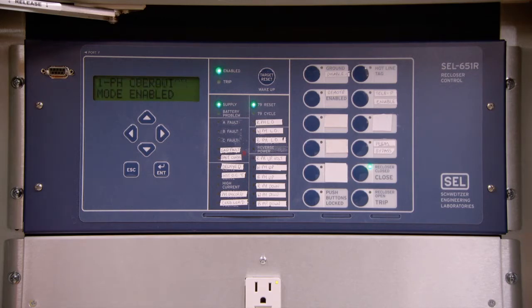Single-phase operation mode. The single-phase operating mode tells you that this unit is only programmed for single-phase operation. That is, it will not operate as a gang-operated unit, meaning that all 3 phases will not trip together. Single-phase lockout mode. Single-phase lockout mode refers to the situation that when this unit enters lockout condition, it will only lock out the phase that was faulted and not all 3.